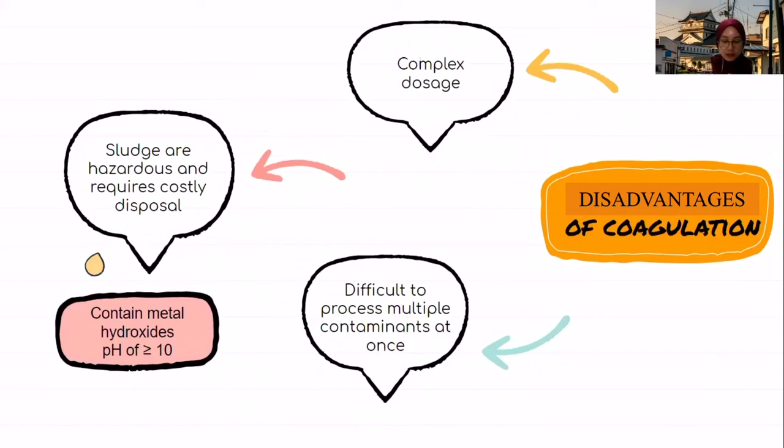The fifth disadvantage of coagulation is the complex dosage. In order to assure that the chemical coagulation water treatment process performs optimally, the correct dosages of the additive constituents must be considered. The rate and efficiency of the process can vary depending on the pH of the solution. Therefore, acid or bases must be added to ensure that the pH is at a neutral level. After this step, the coagulant must be introduced in the optimal dosage, which is required to ensure that the effluent is fully destabilized.